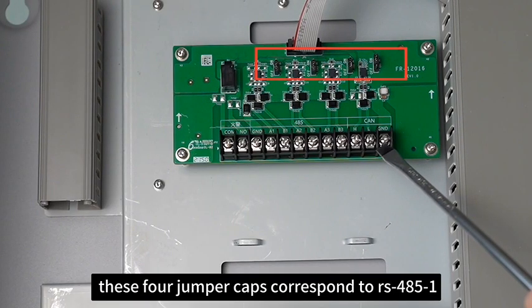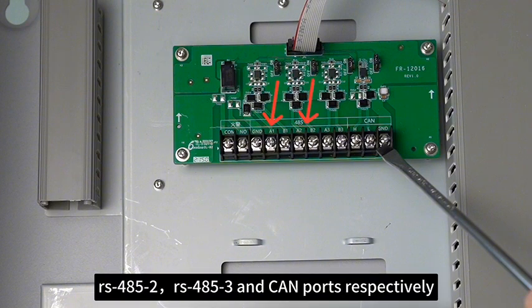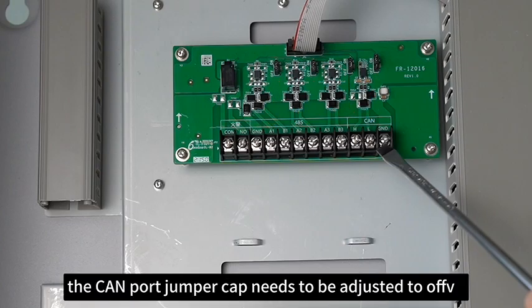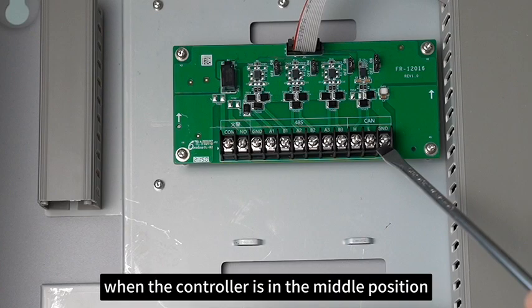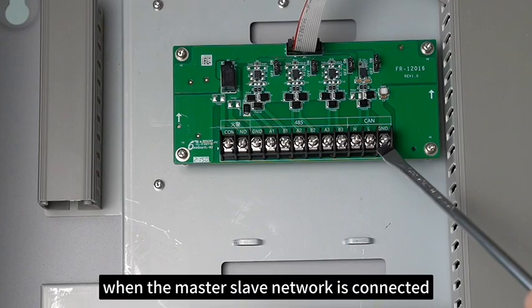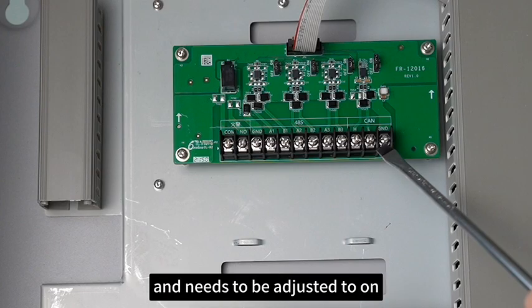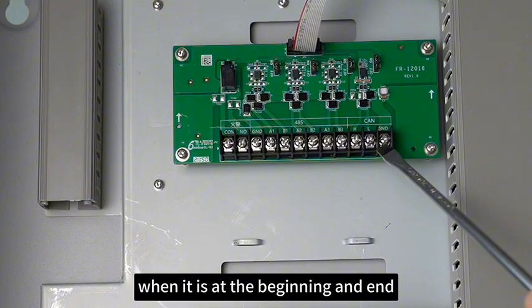These 4 jumper caps correspond to RS-485-1, RS-485-2, RS-485-3, and CAN ports, respectively. The CAN port jumper cap needs to be adjusted to off when the controller is in the middle position when the master-slave network is connected, and needs to be adjusted to on when it is at the beginning and end.